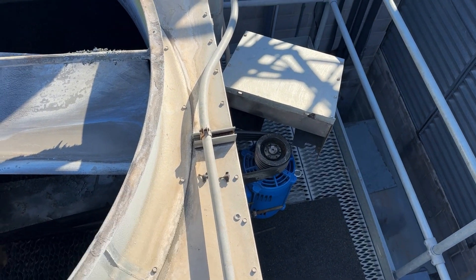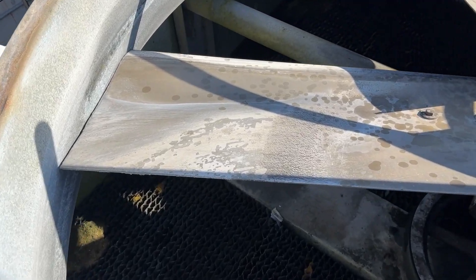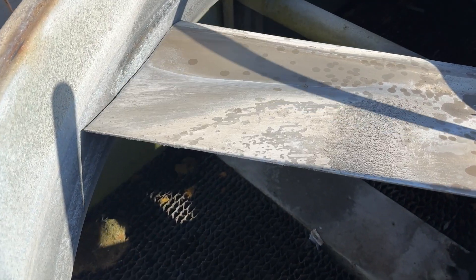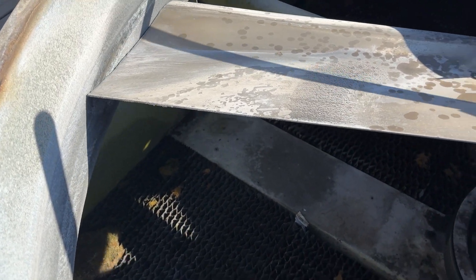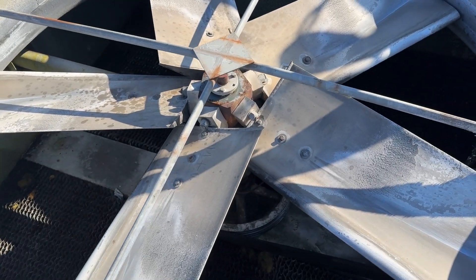Recently I got a code for this motor here being overcurrent. It's no surprise when you got a fan blade scraping the sidewall like that. So I'm going to get in here and just rebuild this whole thing.